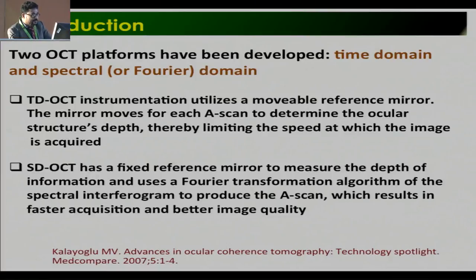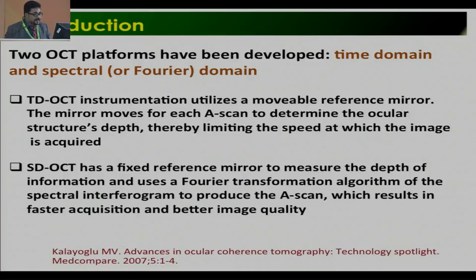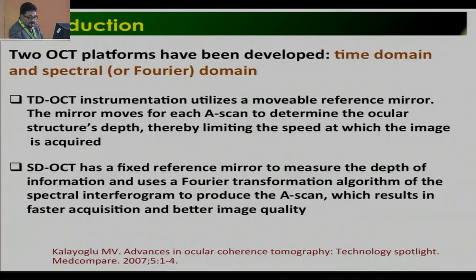There are two OCT platforms that have been developed: time domain and spectral domain, that is Fourier domain. Time domain OCT instrumentation utilizes a movable reference mirror. The mirror moves for each A-scan to determine the ocular structure's depth, thereby limiting the speed of image acquisition. Spectral domain OCT has a fixed reference mirror to measure depth information and uses a Fourier transformation algorithm, producing the scan via spectral interferogram, which results in faster acquisition and better image quality.